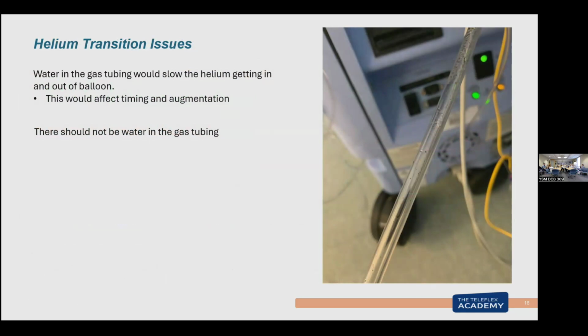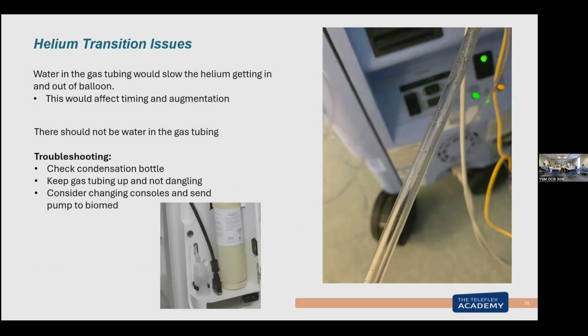Condensation in the tubing, again, can affect my helium getting in and out. So again, we do check this between, and I live in Colorado. We have really dry humidity. We don't have a lot of humidity, so I'm not going to have a lot of extra condensation in my bottle. But you guys have humidity at times here. You may get more condensation than I'm used to. I worked in Pittsburgh one summer. We got 30 cc's of condensation in the bottle every shift. So we got used to checking and emptying that, because if I have condensation, that's going to slow my helium getting in and out and affect my augmentation, my timing and my alarms.